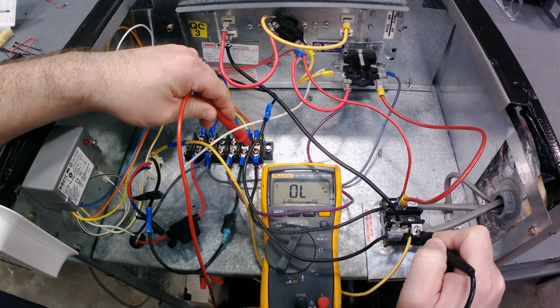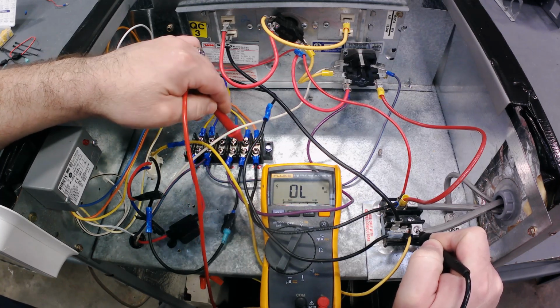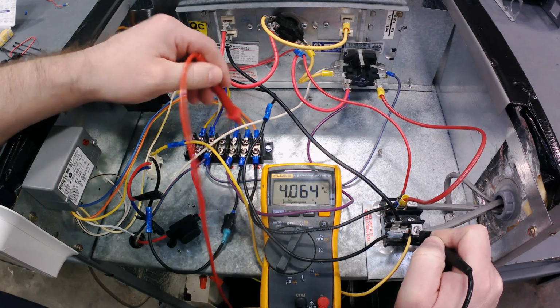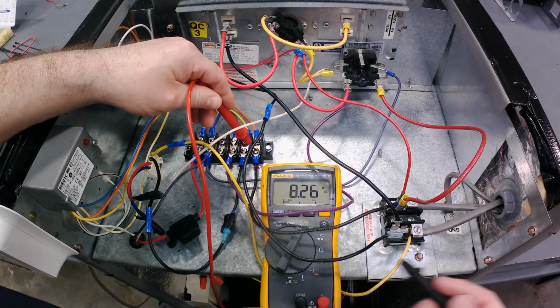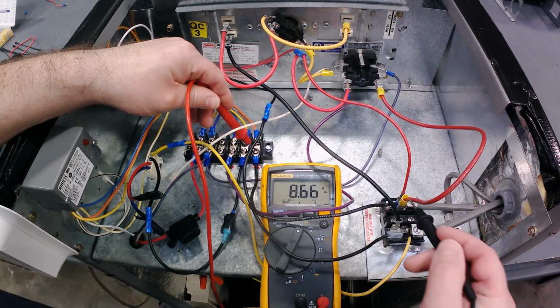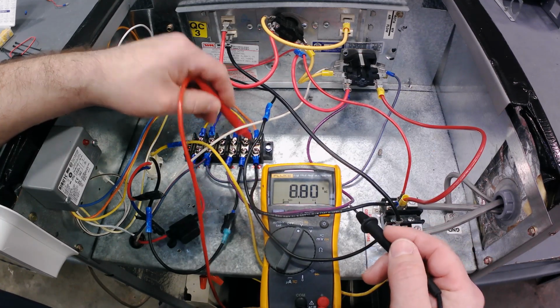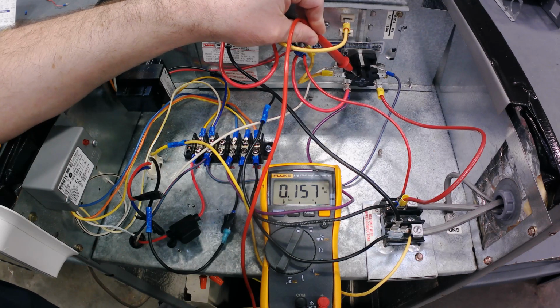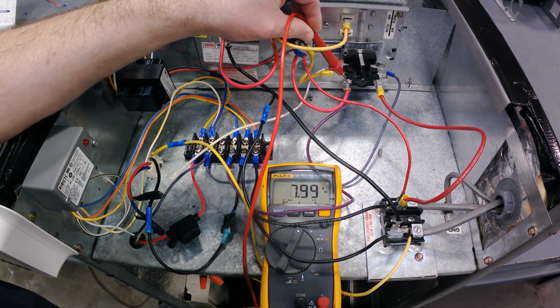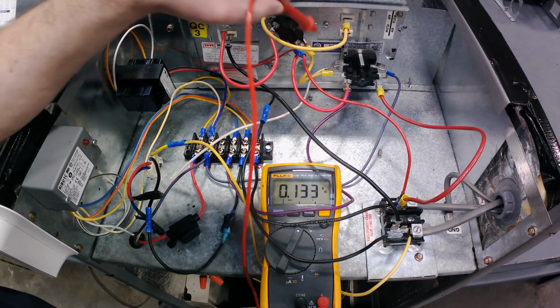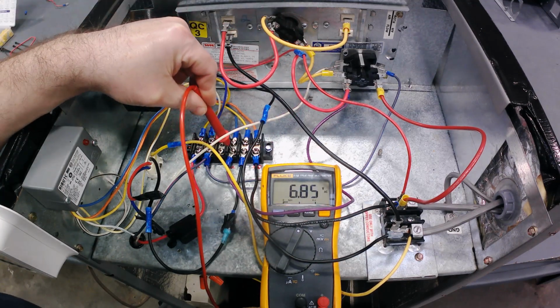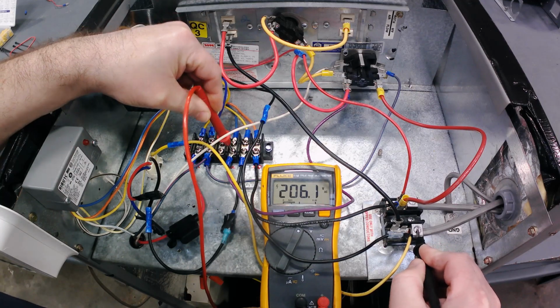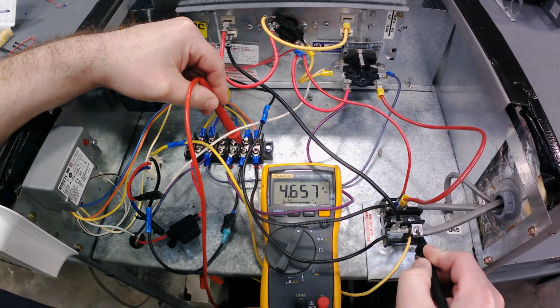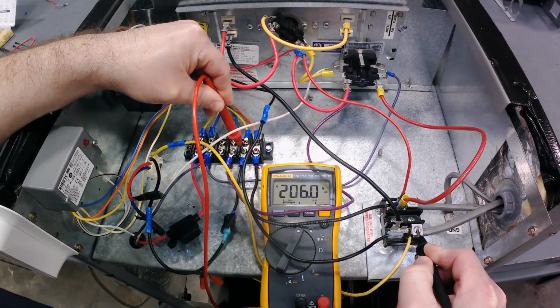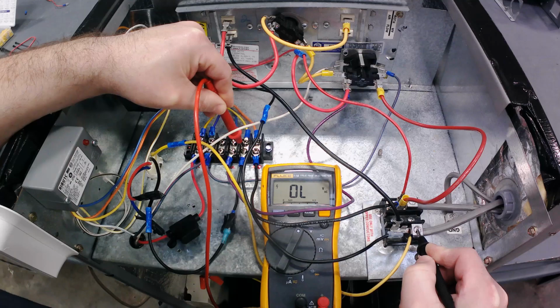So basically, all three of these right now will read power because they're all actually touching L1. The normally open has L1 coming from the terminal block right here on that wire, so I'm just on the opposite end of where the wire connects. The purple has L1 because my heat relay is sending power across the sequencer switch, and when this heater starts power here on this red wire, it also sends power down that purple one. So it's also an active L1, you could say. And then my common, being the way out of this rib relay, is my high voltage coming out. So my fan is on, and I've got power on that common too.